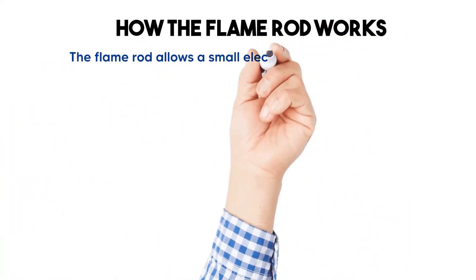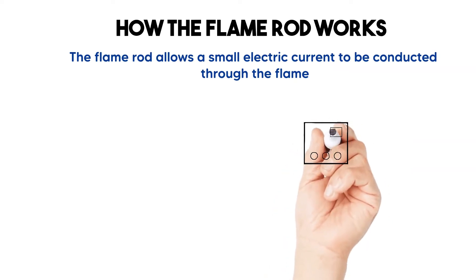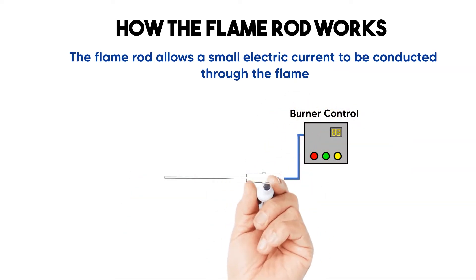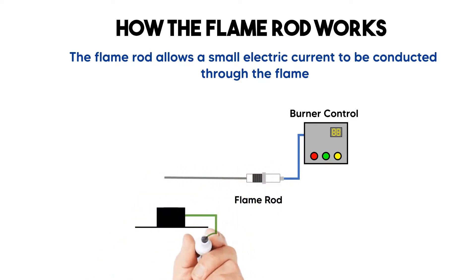How the flame rod works. The flame rod or ionization detector allows a small electric current to be conducted through the flame. To achieve this it is necessary to place the rod so it touches the flame so that the current flows from this rod to the ground through the flame.